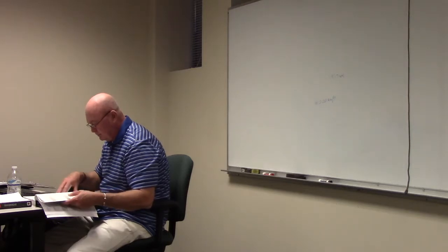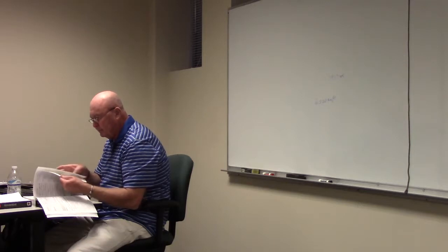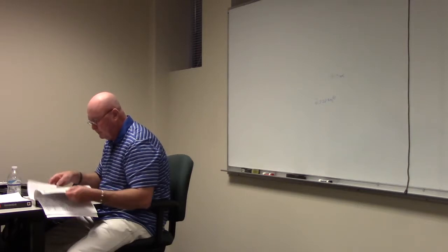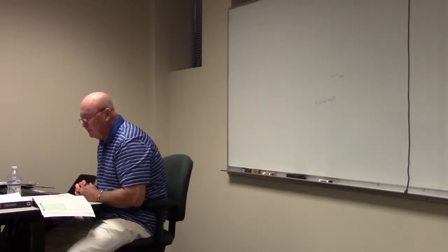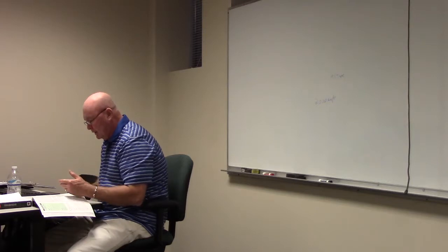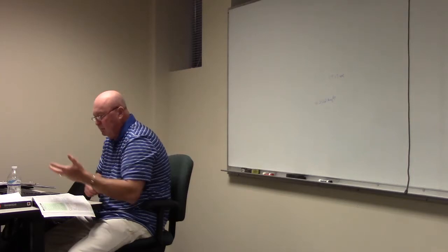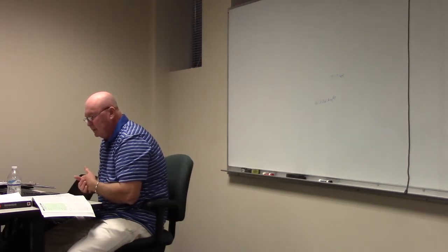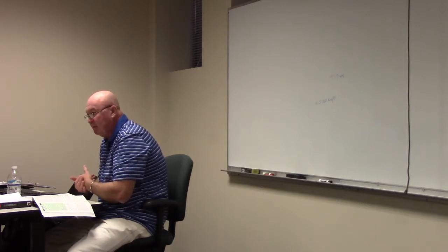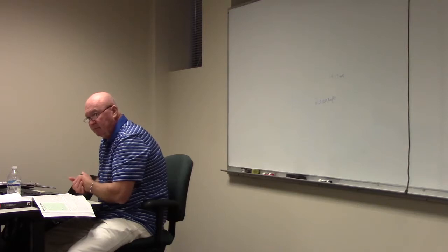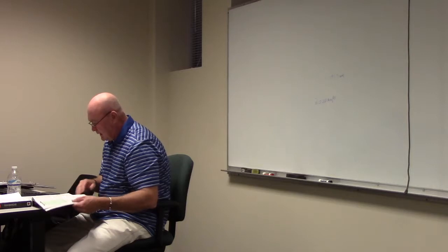3.1.3, which is page 29. I want you to be able to calculate the load on a show window. Like that one there, it's 55 foot. 55 foot times 200 VA, isn't it? Know how to do that. Know that a show window is how many VA per foot? 200, right? Okay. So know how to do that? You can highlight that there.